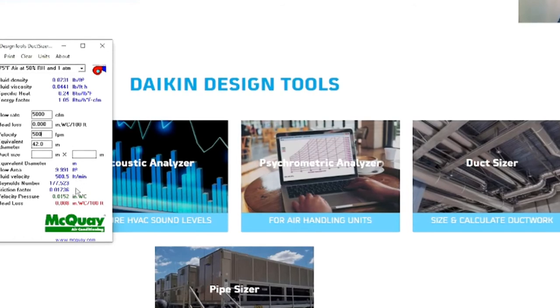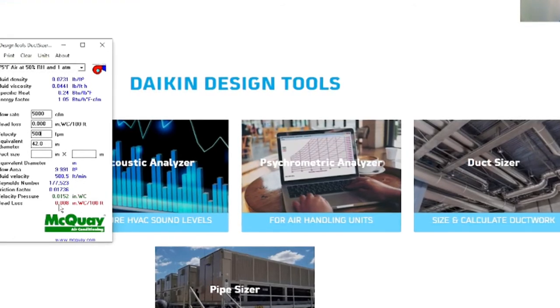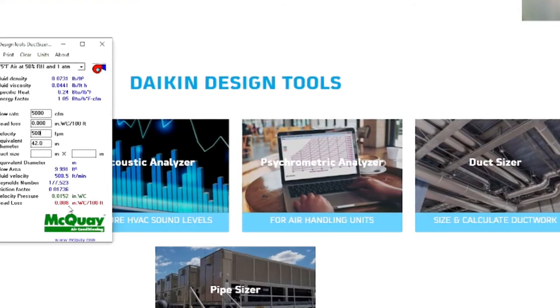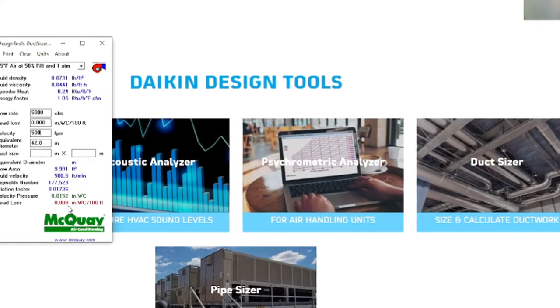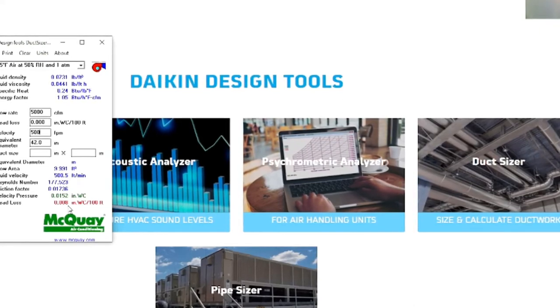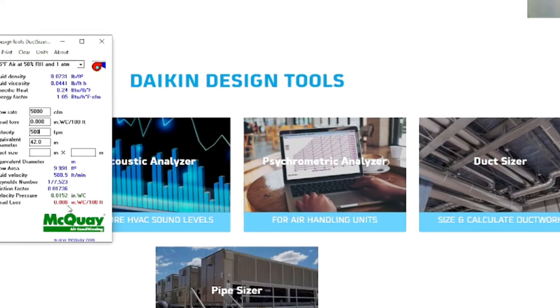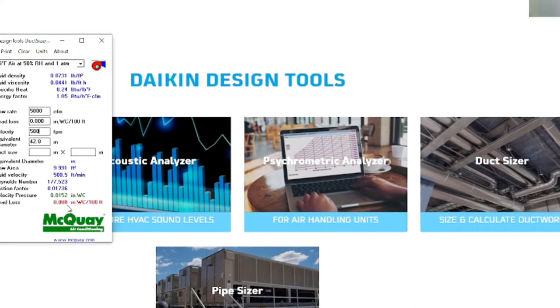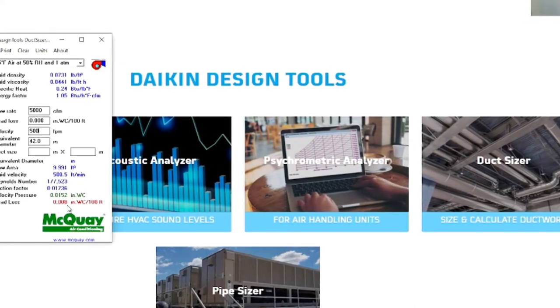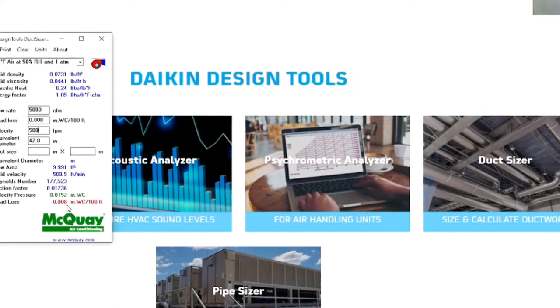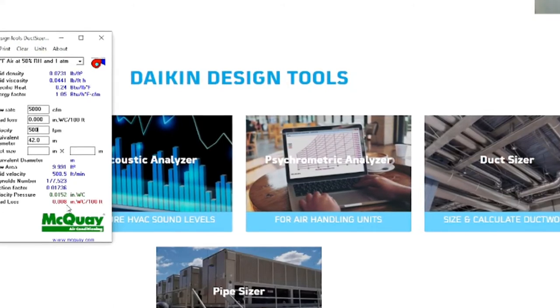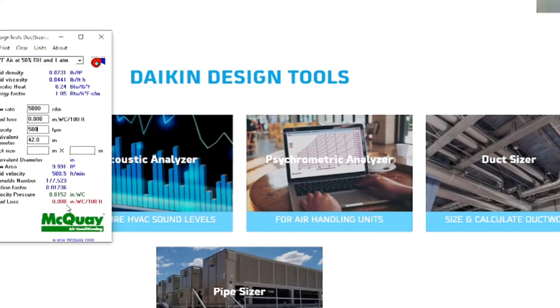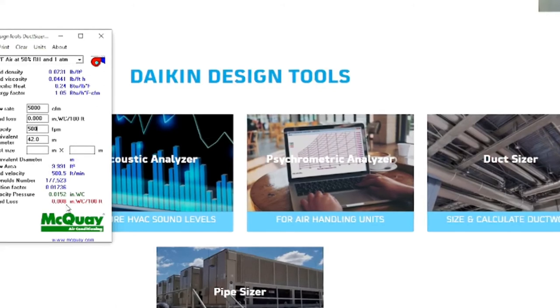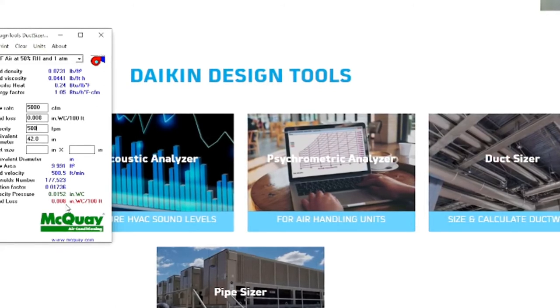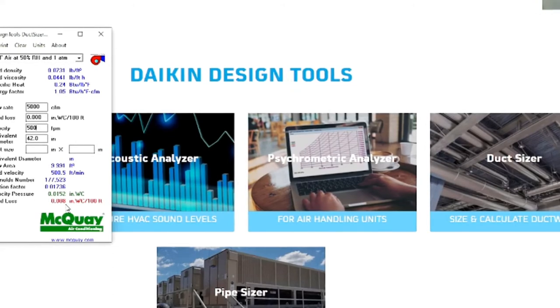And then it also gives you the head loss in the red color in here. Your head loss of the air would be 0.008 inch of water column per 100 feet. So it means that at 100 feet of circular duct at the size of 42.8, you would have 0.008 inch of water column pressure drop across your ductwork.